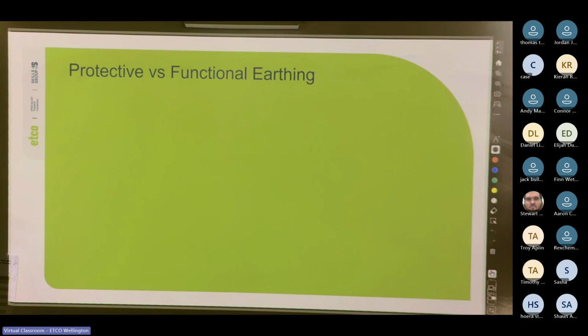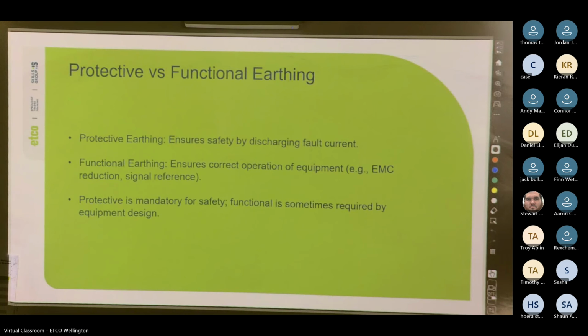So most of the time we're talking about protective earthing, making it safe. But some equipment like electronics also needs the functional earth, which is about performance rather than shock. A protective earth conductor ensures safety by discharging fault current. Functional earthing ensures correct operation, so electromagnetic compatibility (EMC) reduction and signal reference. Protective is mandatory for safety. Functional is something required by the equipment design.